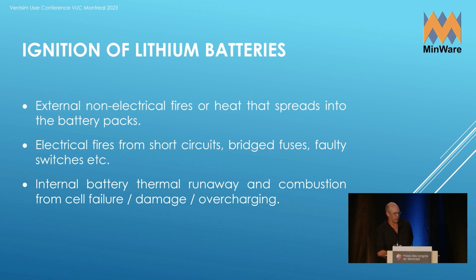In terms of how batteries catch fire, there's a few different ways. You can apply an external heat source that spreads to the battery pack once it gets hot enough. You can also start electrical fires through short circuits, failed switches, or failed fuses. There's another phenomenon called internal battery thermal runaway, where the internal chemistry starts to short circuit itself, and the kinetic load of the electrical energy creates its own heat source, causing a thermal runaway that spreads to the entire battery and causes it to fail and catch fire. That can result from damage, overcharging, failure of the cooling system, or failure of the computer to keep the battery voltage at correct levels.